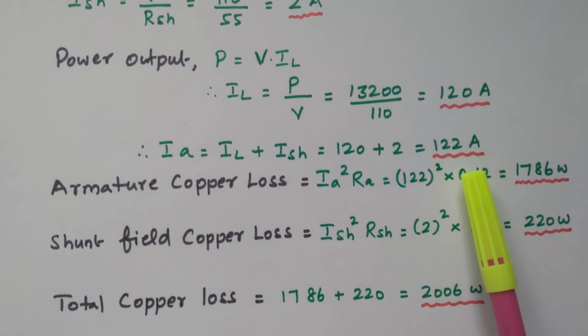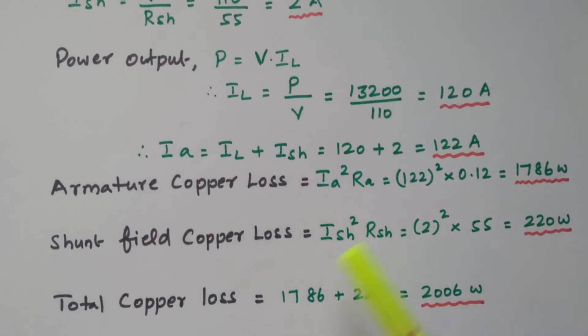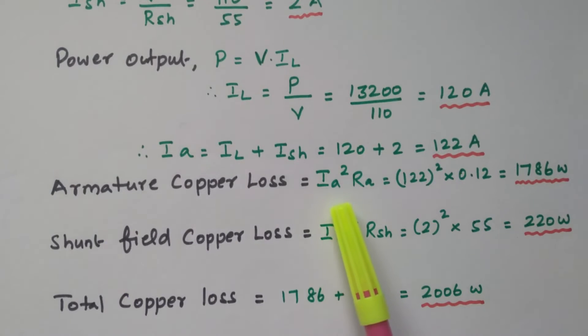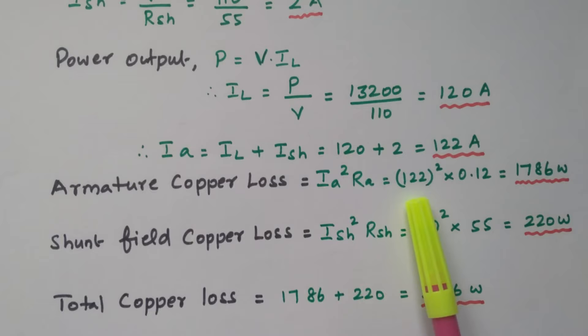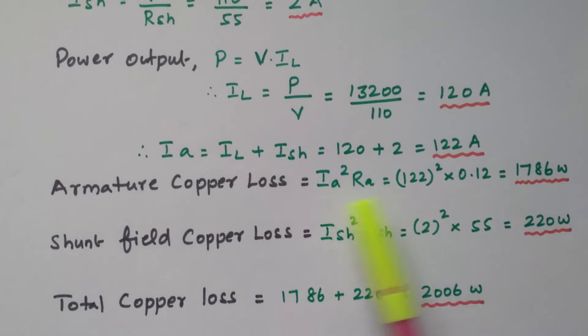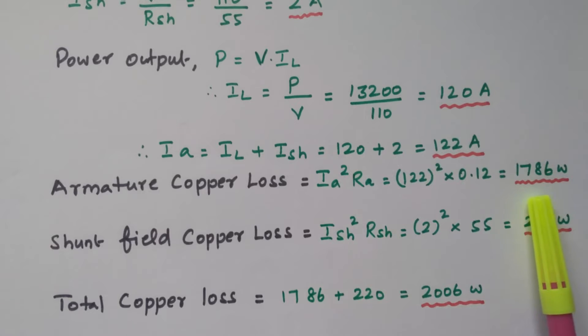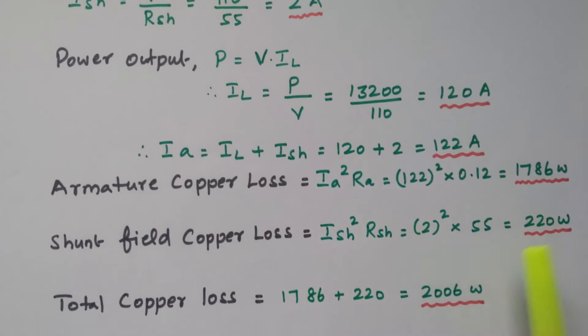With this armature value we can calculate the copper losses one by one. Armature copper loss = Ia² × Ra. The formula for armature copper loss is Ia² × Ra. So that is 122² × 0.12, which equals 1,786 watts armature copper loss.